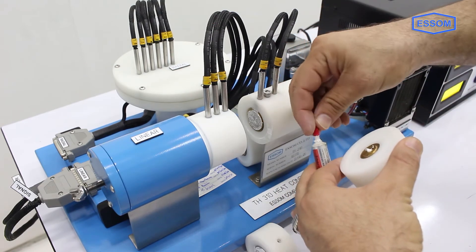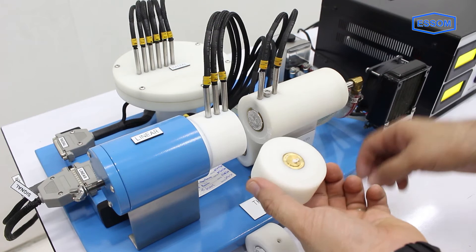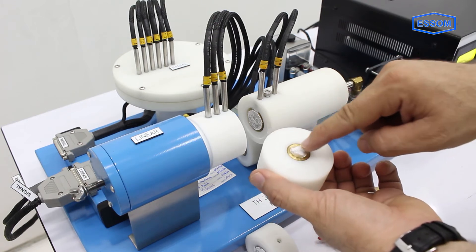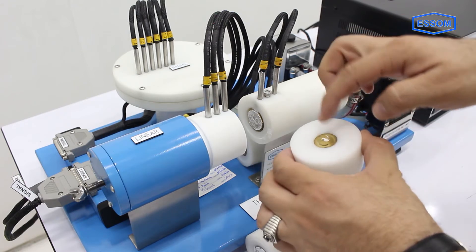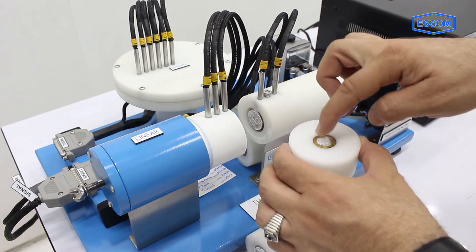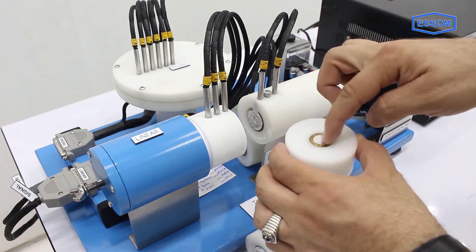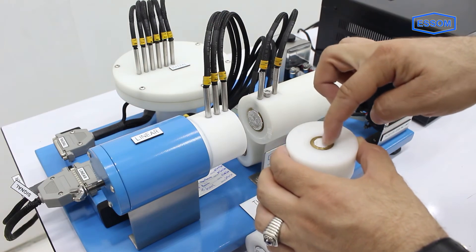Matching surfaces of the heat conduction section are accurately finished to minimize conduction resistance, and a heat conducting compound may be applied to further reduce resistance. Thermal conductivity of an insulation material can be determined by inserting a thin insulating disc between two heat conduction surfaces.